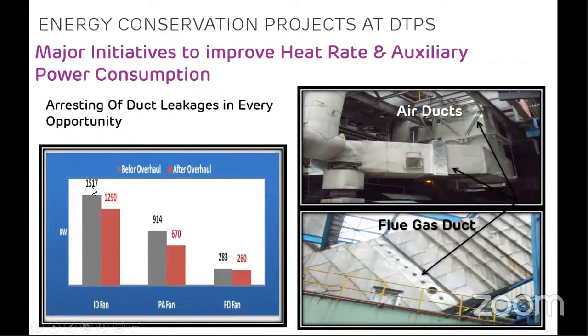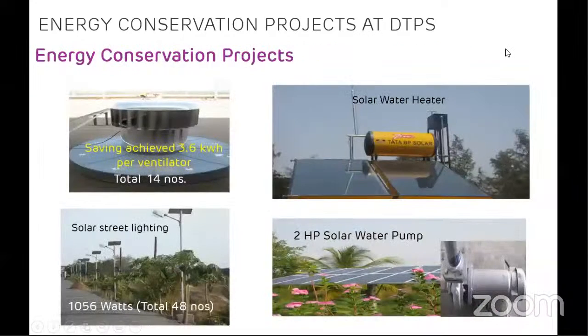Here you can see the ID fan loading was reduced from 1517 kilowatt to 1290 kilowatt. PA fan loading was reduced from 914 kilowatt to 670 kilowatt, and FD fan loading was reduced from 283 to 260 kilowatt. So these were some of the major initiatives which we used for energy conservation. Most of these were based on maintenance, like modifications or process alterations during the overhauling of the equipment, which led to lower energy consumption and better heat rate.